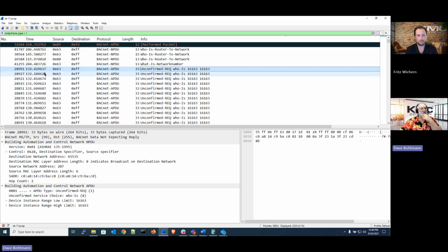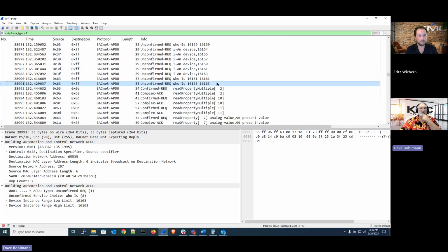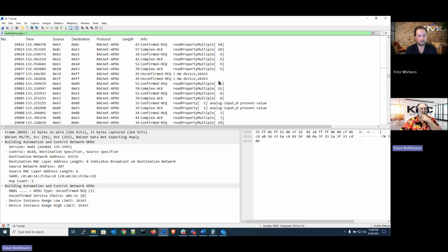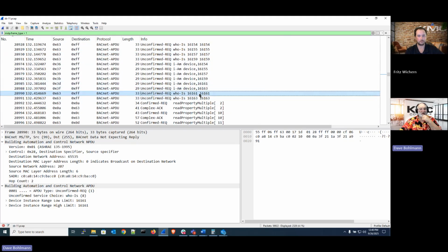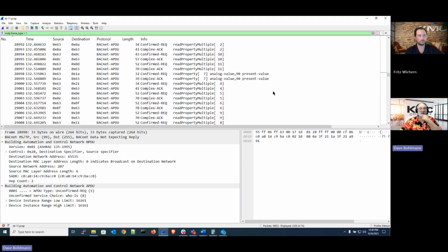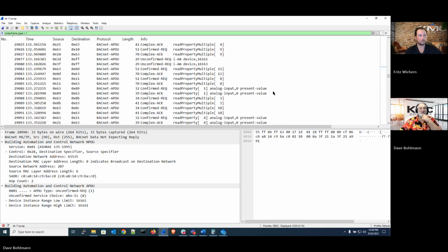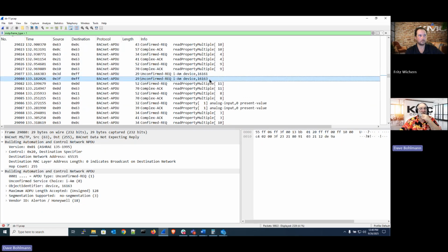But the odd thing is, it sends out the Who-Is, and then, let me see if I can. Yeah, okay. I was going to say it sends it out again pretty quickly. But the odd thing is here it sent one out to 16161 and 16163, and then here is the response from both of them.